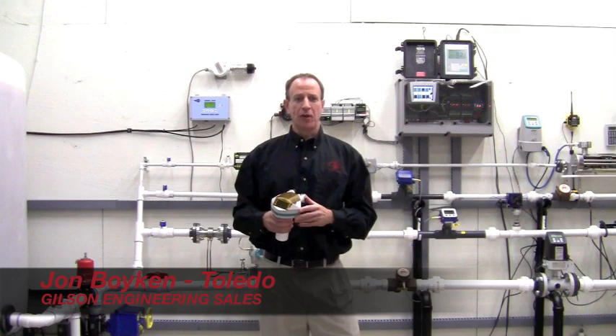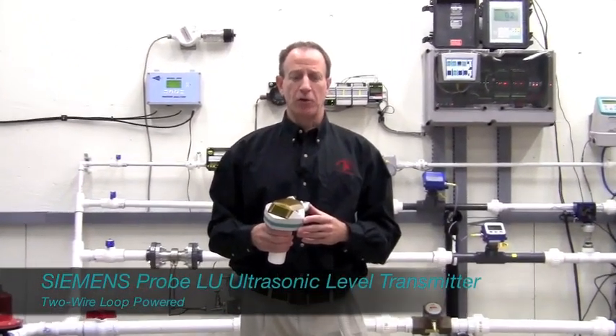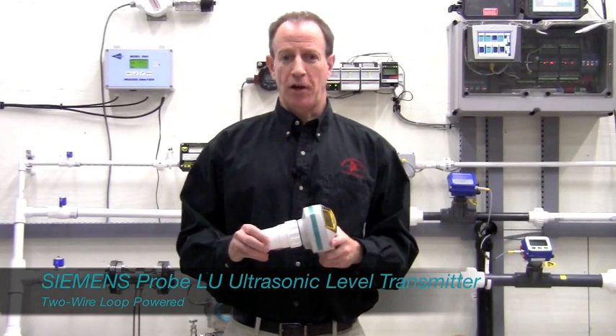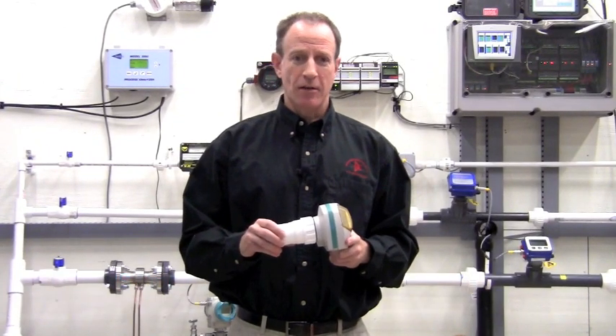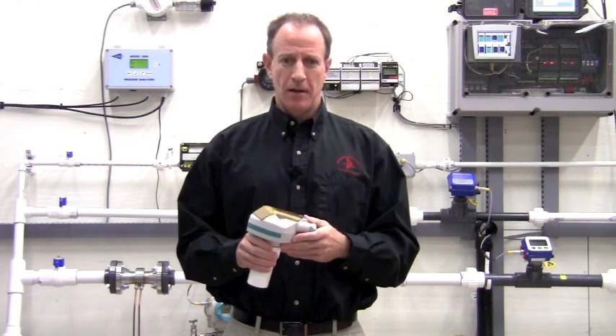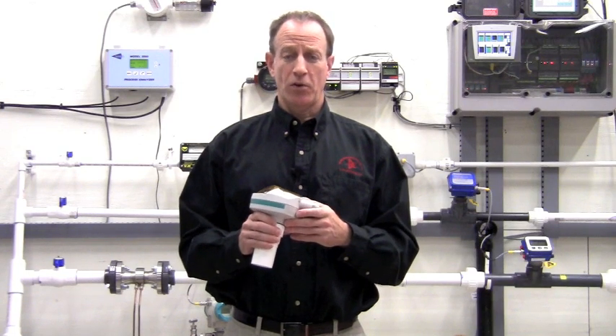Hi, I'm John Boykin from the Gilson Engineering Toledo, Ohio office. Today I'd like to talk to you about the Siemens Probe LU Ultrasonic Level Transmitter. The Probe LU is a two-wire transmitter available in ranges of 19 foot or 39 foot. HART protocol is standard and Profibus is an option. The sensor may be made from Kynar or Teflon.